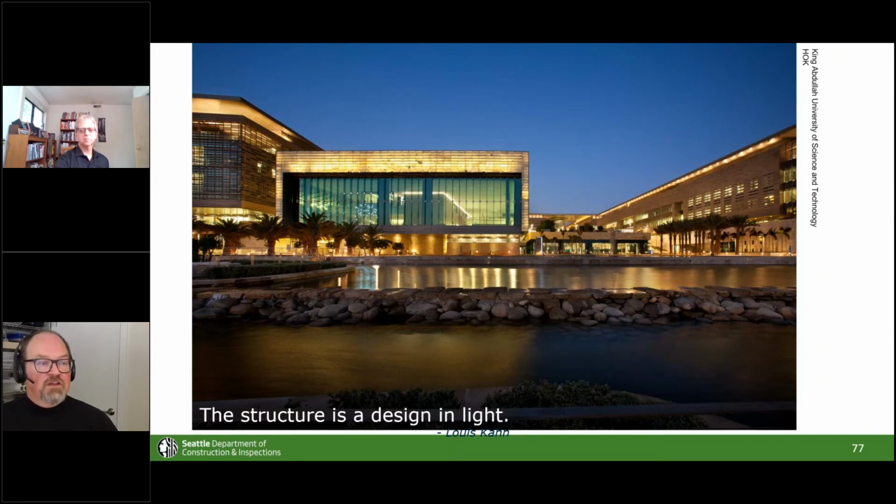Every single light fixture you see here is dimmable, including the outdoor ones. Every single light fixture is controlled with a networked lighting control system, 20 buildings, all able to come to one place. This was a lot of work. 3 years of my life went into designing this and the control system for this, but it's doable, right? 10 years ago, this would not have been possible. I wouldn't say 10 years. 10 years before this would not have been possible. Today, this would be relatively simple. So whatever you're doing retrofitting, make sure that you're trying to leave a better space than you found, right?